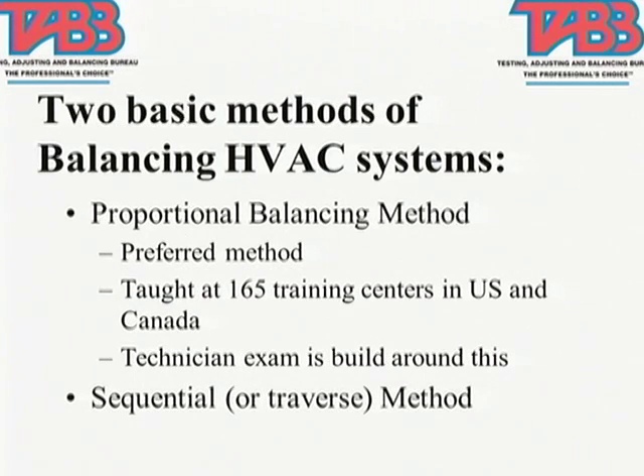Then there's the sequential method of balancing a building, and I used to do some sequential balancing when I was younger, and that is basically by guess and by golly. If I adjust this, what happens? No math, no reason. And I like to say that's how many people used to fix their automobiles before the advent of all the electronics. If your car was running wrong, there was a sequential list you would go down. The first thing was you'd adjust your points, condenser, distributor cap, spark plug wires, and they had a sequential list. And when you magically fixed what was right, it worked. And you may have replaced 3 things that you didn't need to, but we got down and they fixed the problem. So that's the difference between the 2 methods.